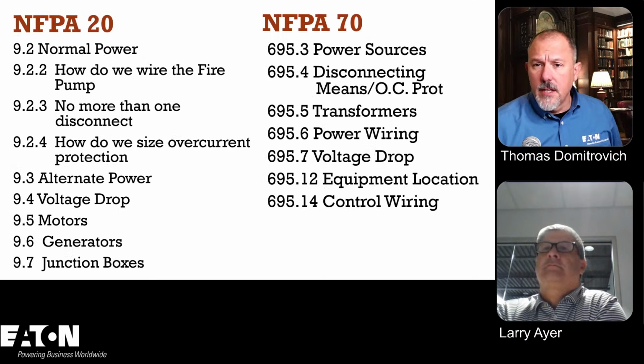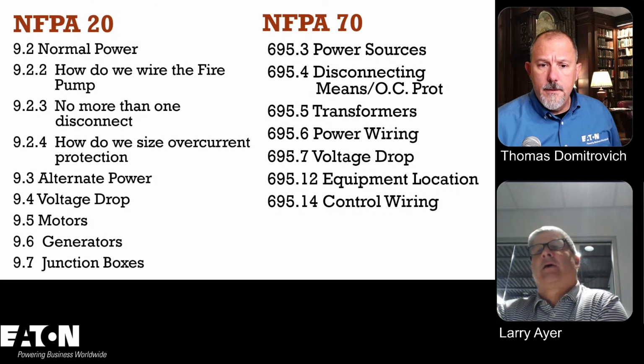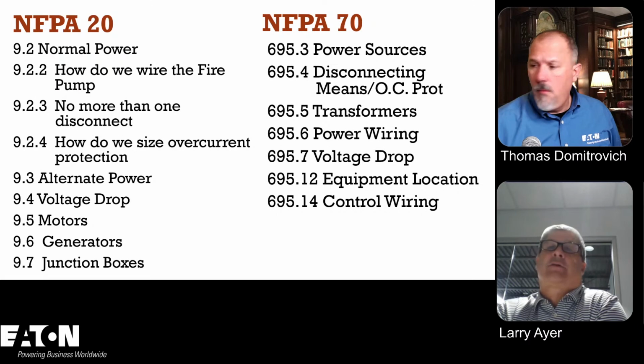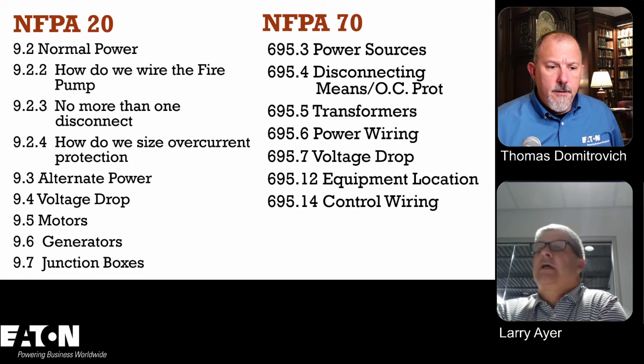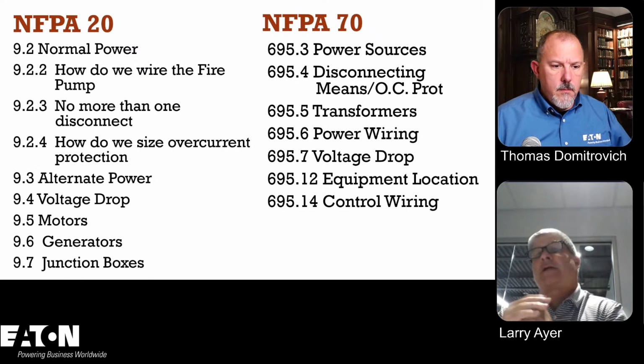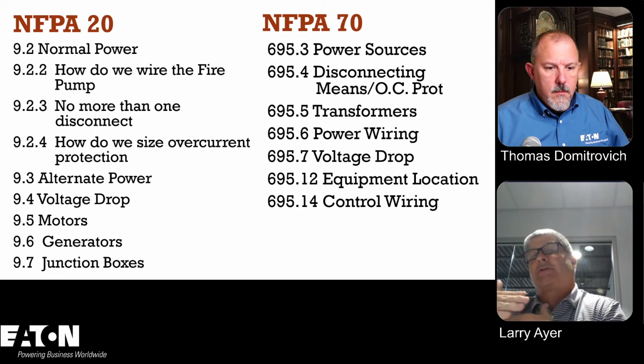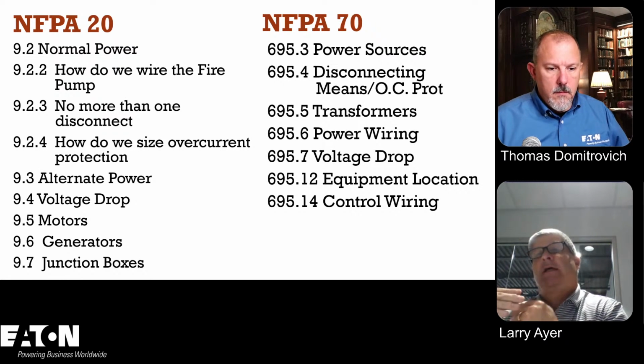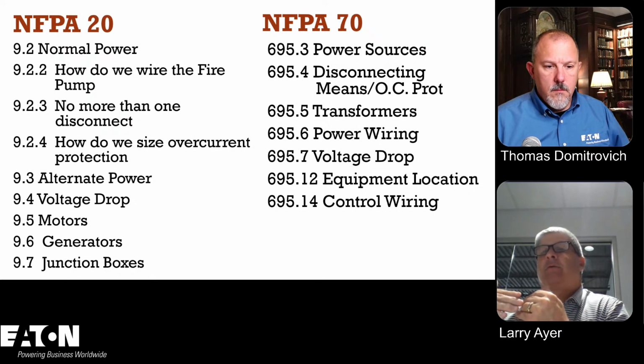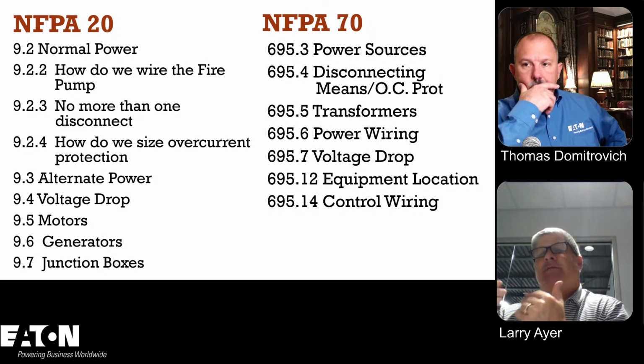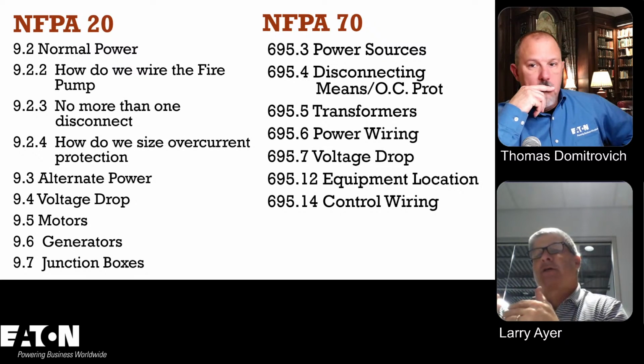Oh, okay. So this is a little comparison you put together. I like this. Yeah, and hopefully it's helpful to the person that's listening here or the user. So what you look at here is, when we start off, we had the general requirements in NFPA 20, and then we moved to 9.2, which is normal power, and says, okay, how do we wire the fire pump? 9.3 says, okay, what are the alternate power sources we can use, and why would you use one? And we have voltage drop. Then we go to motors, generators, junction boxes.